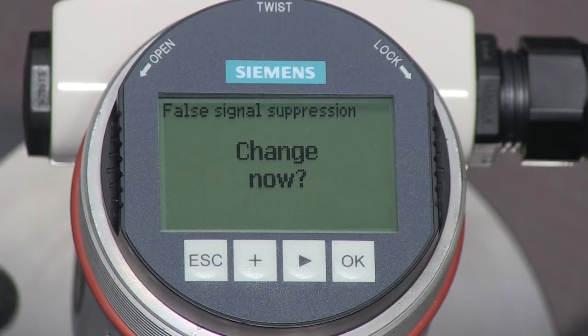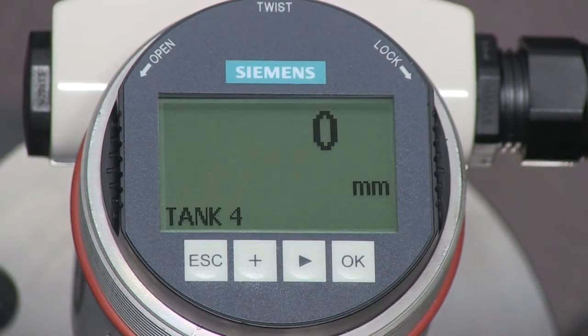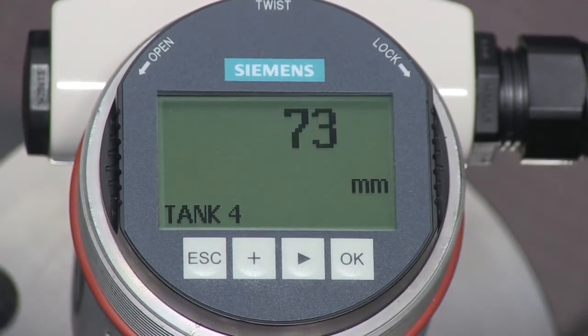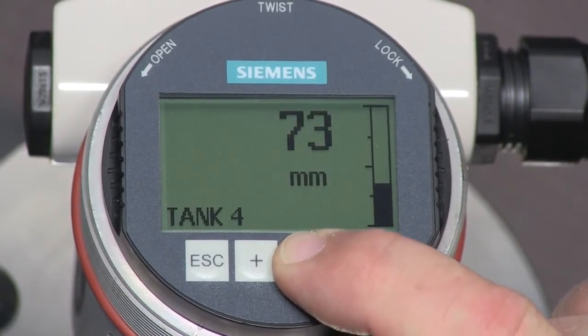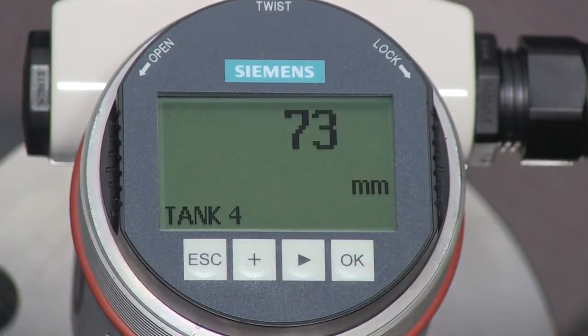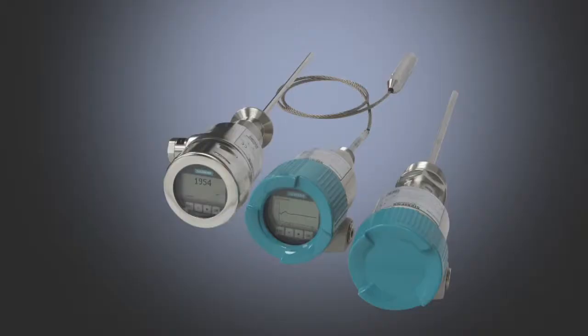Our tank does not have any obstructions, so we will leave this parameter set to the factory default. The SITRANS LG250 is now configured for our application. The measured level value can be displayed as a single value, alongside a bar graph representing the tank, or as a measured value along with a secondary value such as the transmitter temperature. The choice is yours. For more information on the SITRANS LG250, please visit our website.